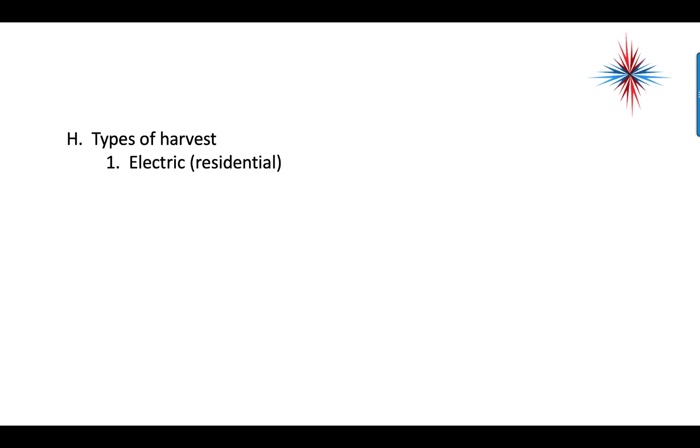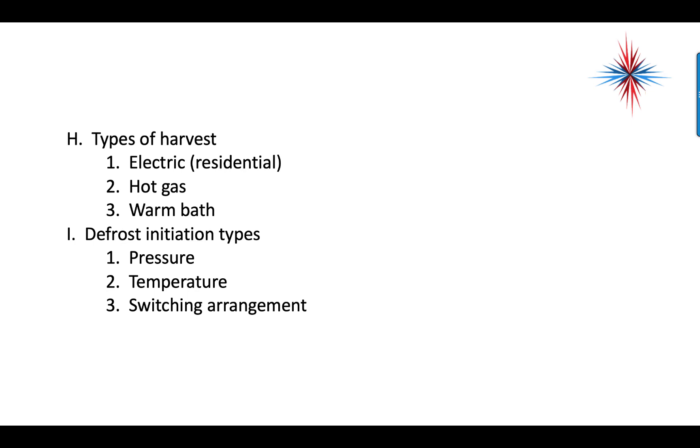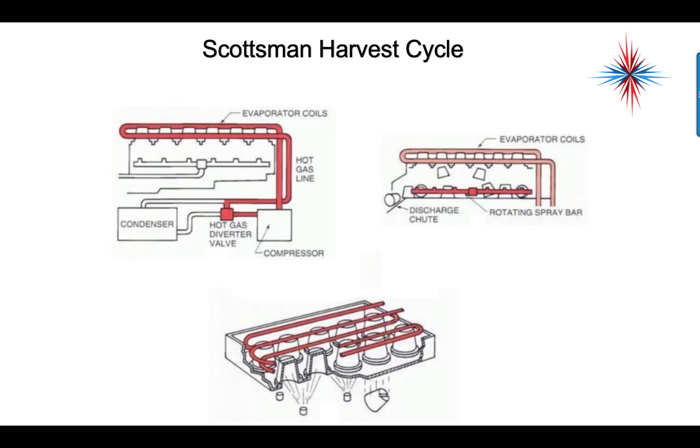The types of harvest could be electric, most often seen in residential ice machines; hot gas, most often seen in commercial; or a warm bath, which I haven't seen in years. Defrost initiation, which is harvest initiation, could be done by pressure, could be done by temperature, and could be done by a switching arrangement, which could be a probe or a timer.